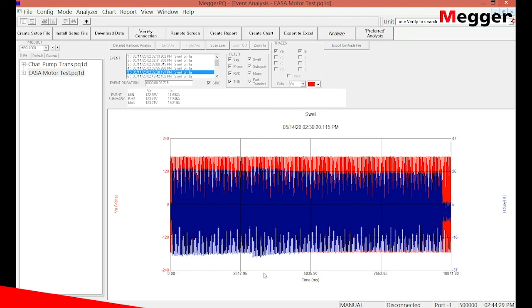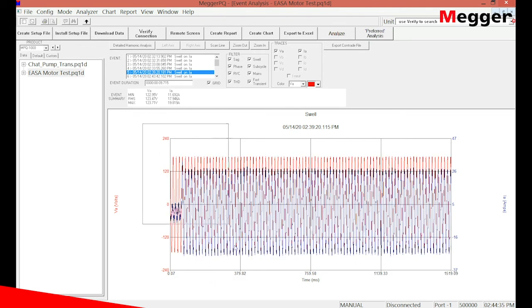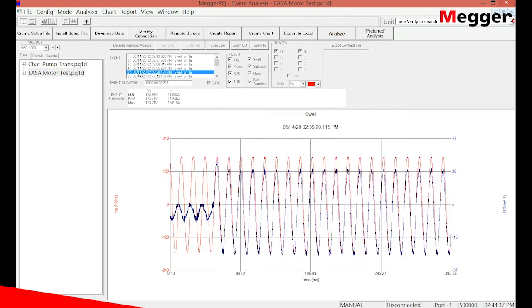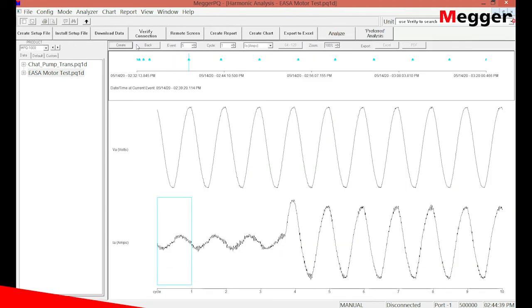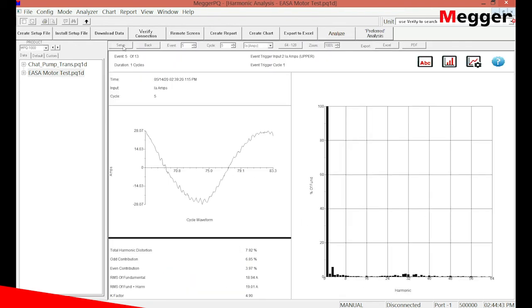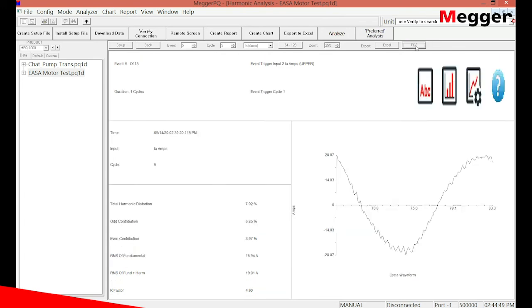And you can clearly see these waveforms are 10 seconds long. We can zoom into each waveform and analyze it. We can create a harmonic analysis by clicking on a button. Now we select the cycle and view the harmonic data for this inrush. I can then create a harmonic analysis report with a simple push of a button.